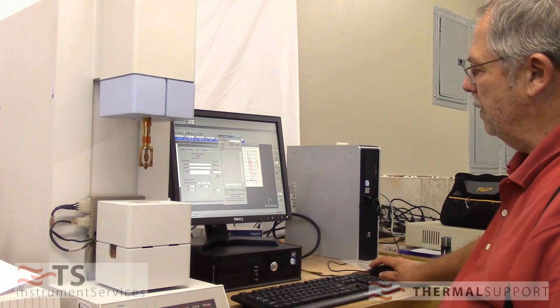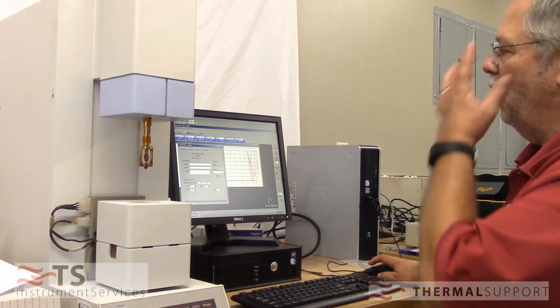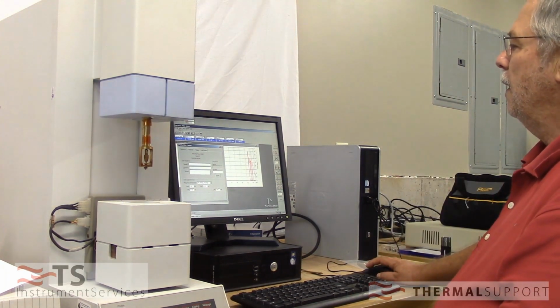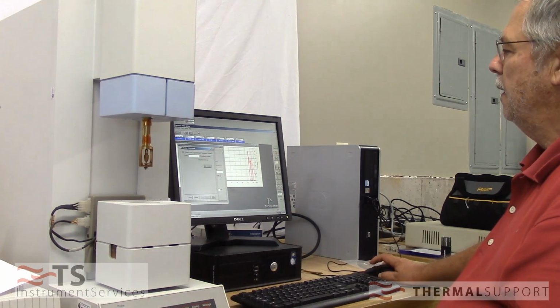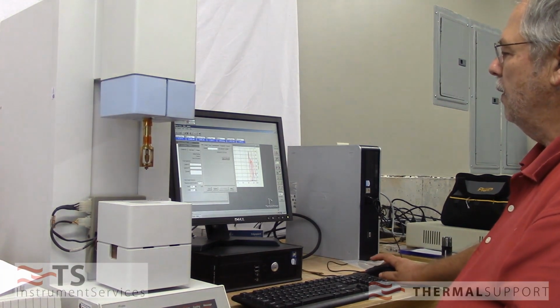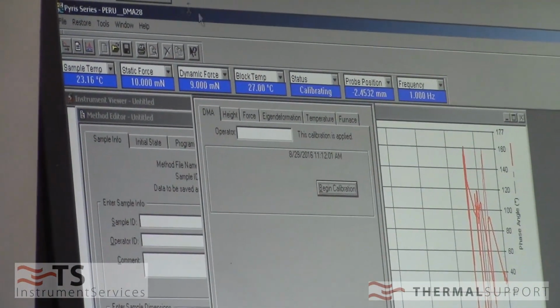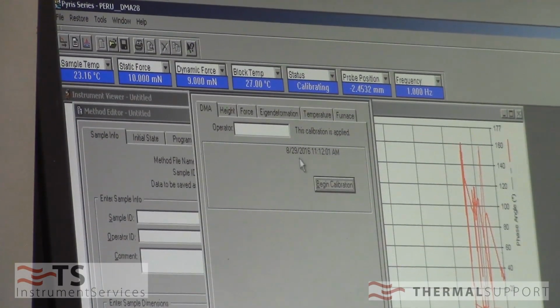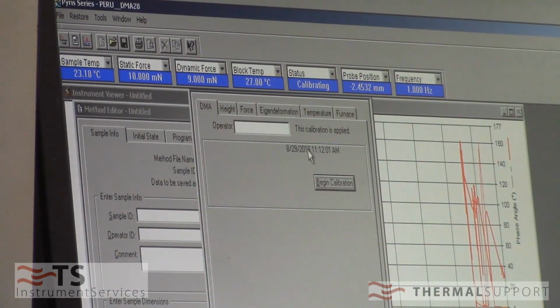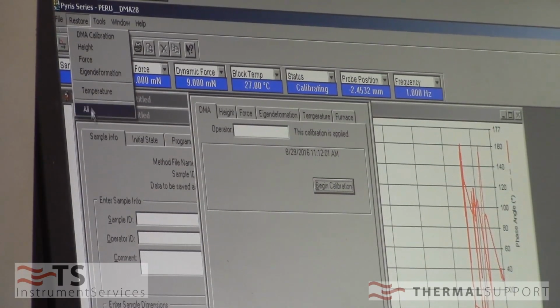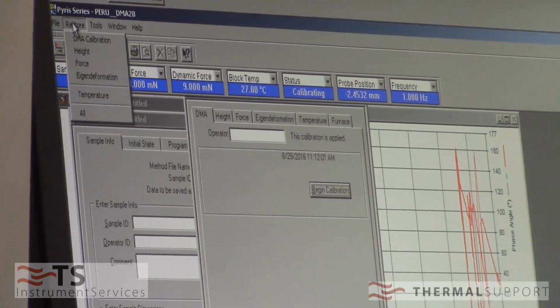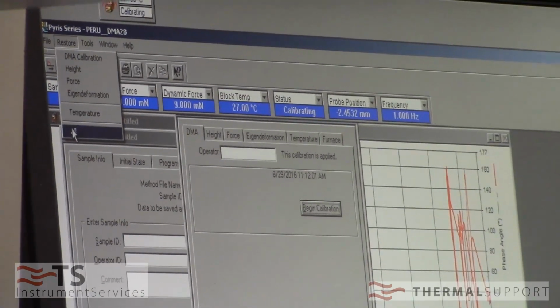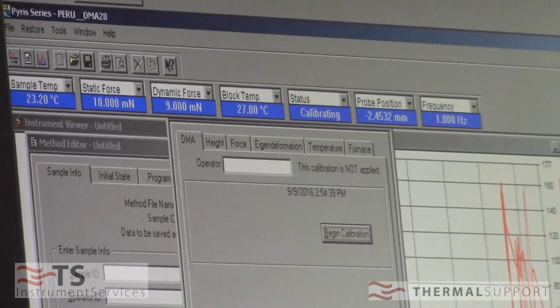So I'm going to close out this, and I'm going to go to the top file menu bar while we're under method, and I'm going to view calibrate, and here we have a calibration that was done the other day. You can see the 8/29/16 that we did. Anytime you start a calibration, what you want to do is restore all your defaults. So we want to restore all. Top file menu bar now is changed, so you restore all. And then we're going to save and apply.